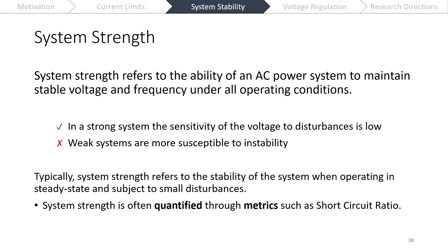Here, SCR, or short circuit ratio, is just defined as the ratio between the short circuit current at that point of interconnection. So something of an idea of how much support it's getting from the other synchronous generators in the system that might be far away. We might have lots of impedance, so we might have a lower short circuit ratio. Or if it's nearby, we usually would have a higher short circuit ratio. And then we compare this to the rating that we have of our inverter device to get an idea of, relative to our device's size and how it's acting, how much support it'll get from devices in the rest of the system. If we have an SCR below 3, we can usually say the system's weak. Above 3, we say the system's strong.